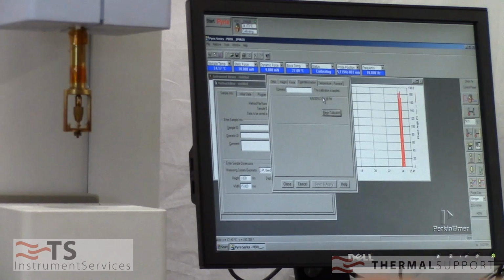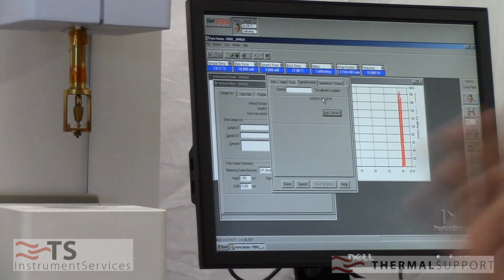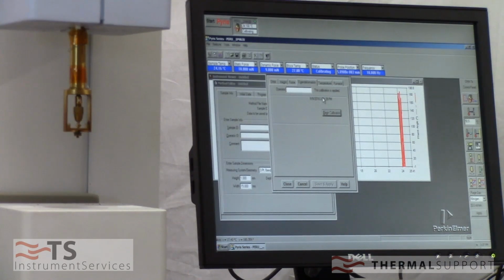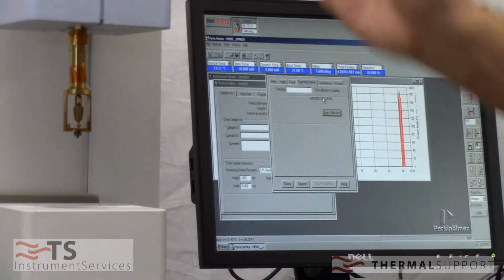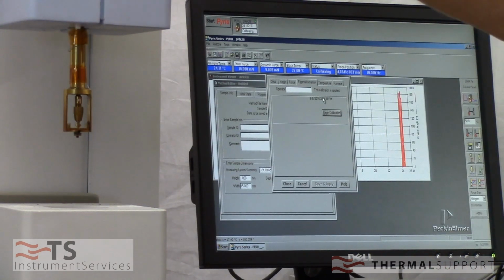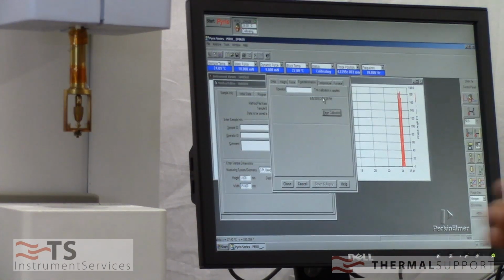This is a great analyzer. It is not a perfect mechanical device. There is no perfect mechanical device. And so the purpose of the eigendeformation is to put a consistent force at zero. We put them on top of a steel slug that's not going to move. It's going to look at any changes it finds in the flexure between the motor itself, the core rod, the probe, the sample tube, anything, and it's going to remember that in the software calibration.